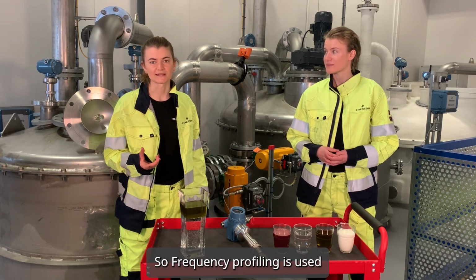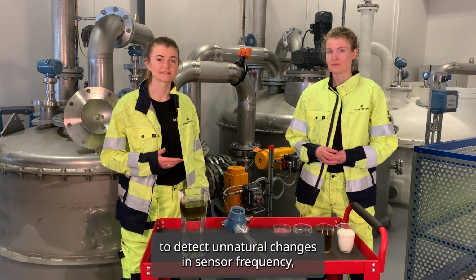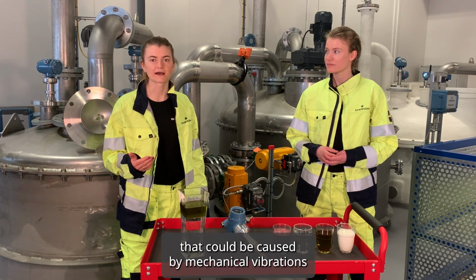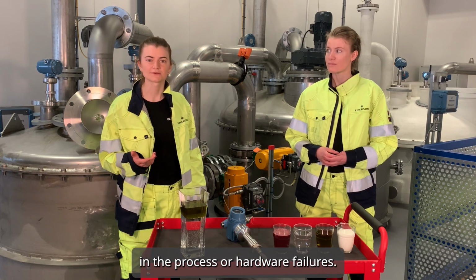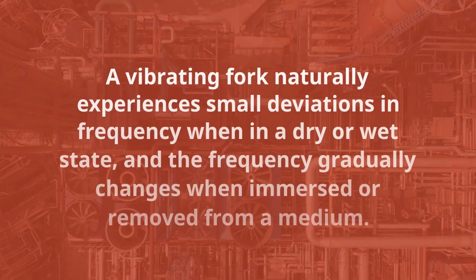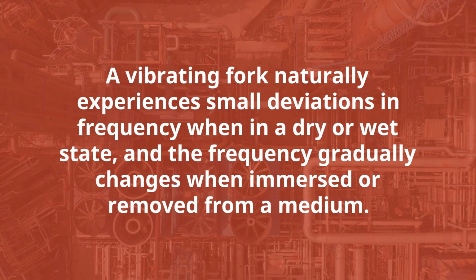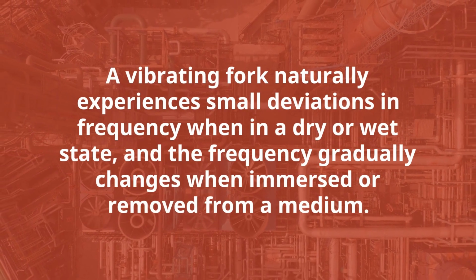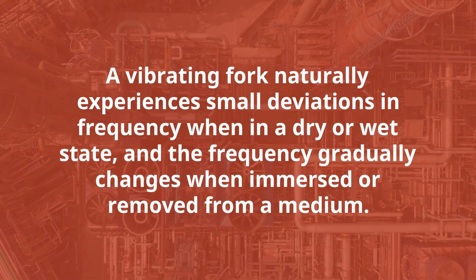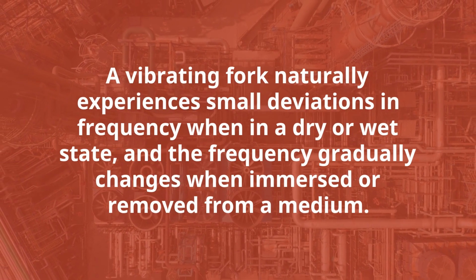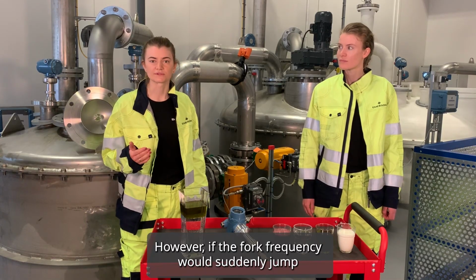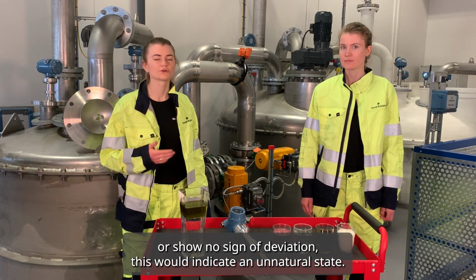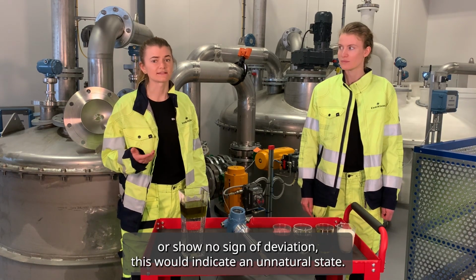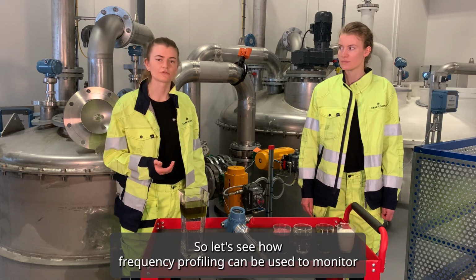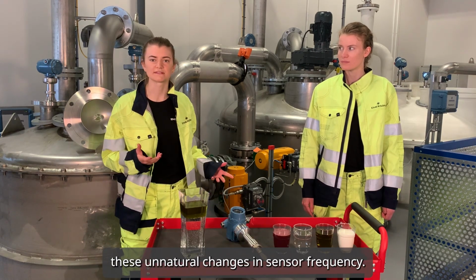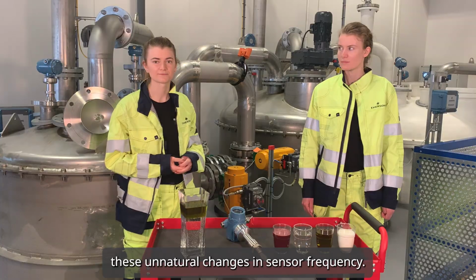So frequency profiling is used to detect unnatural changes in sensor frequency that could be caused by mechanical vibrations in the process or hardware failure, for instance. A vibrating fork naturally experiences small deviations in frequency when in a dry or wet state, and the frequency gradually changes when immersed or removed from a medium. However, if the fork frequency would suddenly jump or show no sign of deviation, this would indicate an unnatural state. So let's see how frequency profiling can be used to monitor these unnatural changes in sensor frequency.